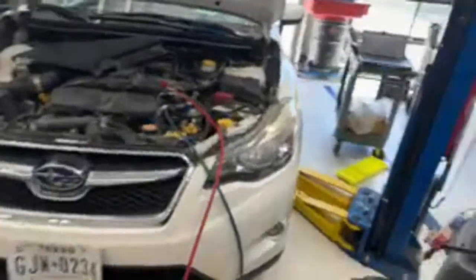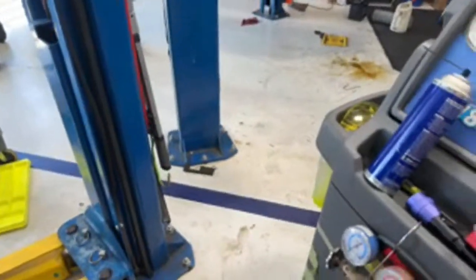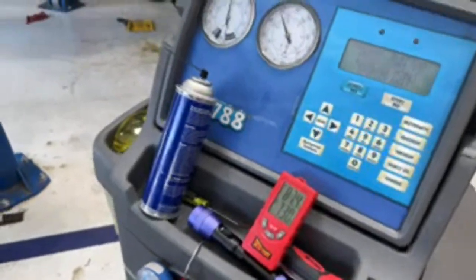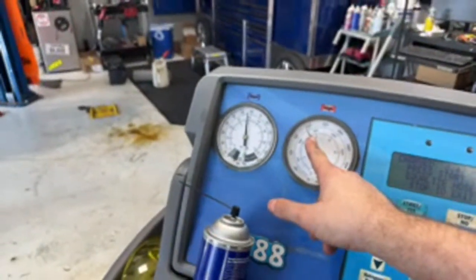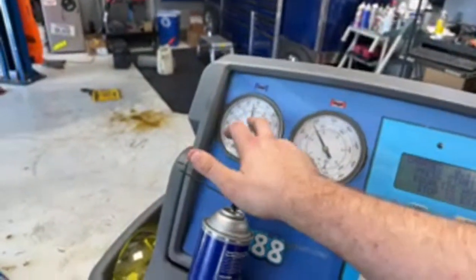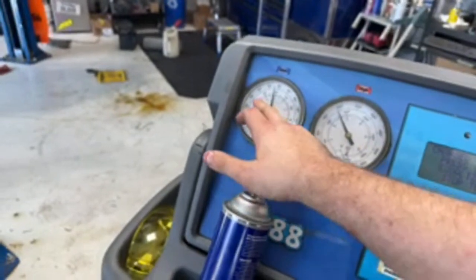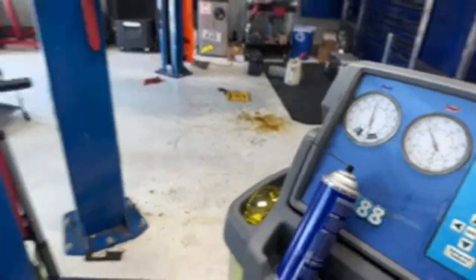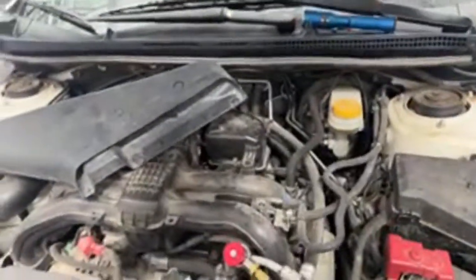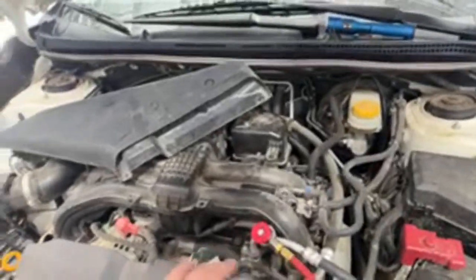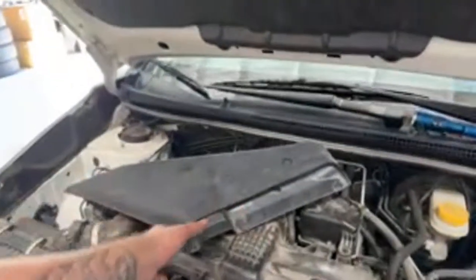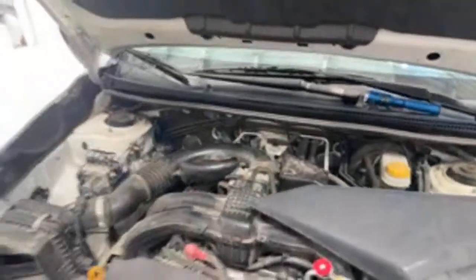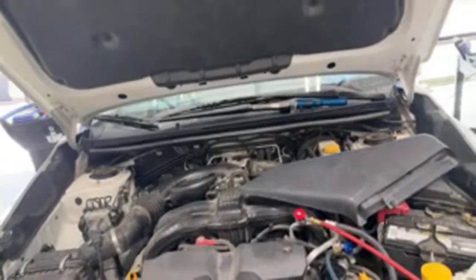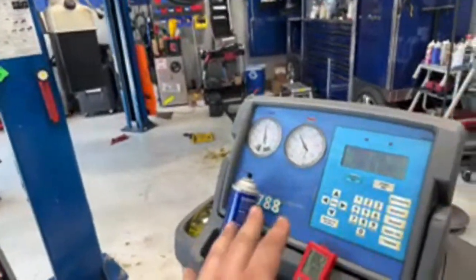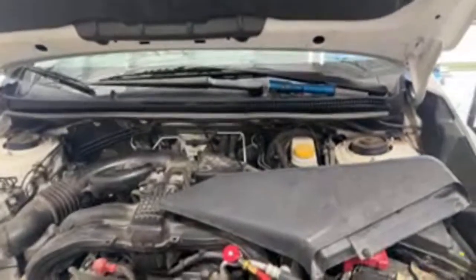All right, let's come and inspect everything. We're only putting out 73 degrees. My high side is 190, okay-ish, but I'm more worried about my low side right here. My low side should be between 30 and 40 psi. The fact that it's hovering at 60 is giving me the indication this may not be sucking all the juice out of the evaporator efficiently. This sometimes can take 5 minutes to equalize, but typically a rev up tune-up gets its butt in the right direction.